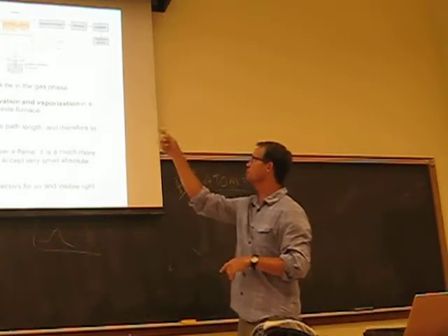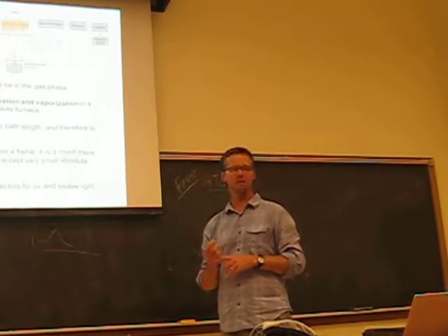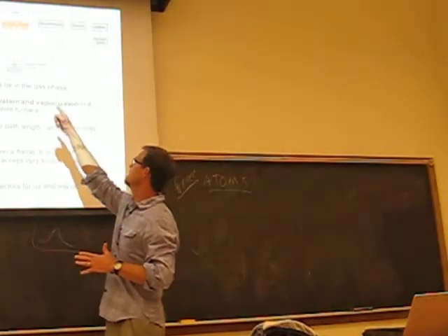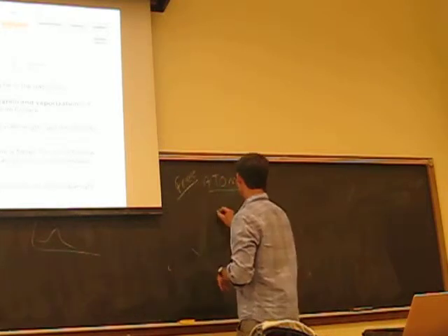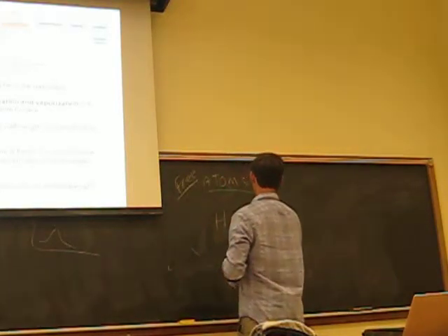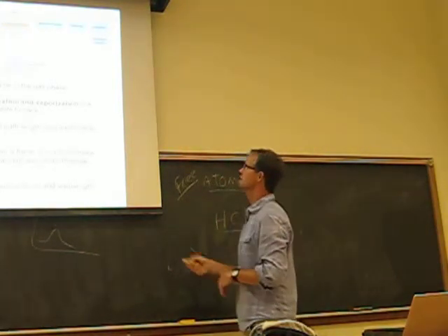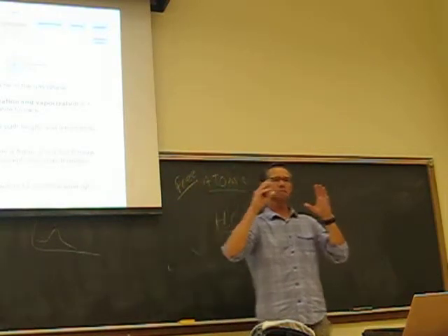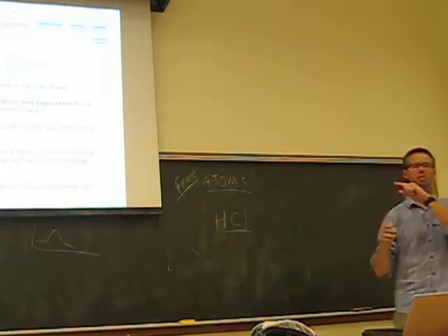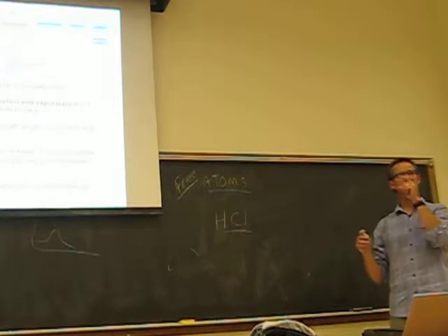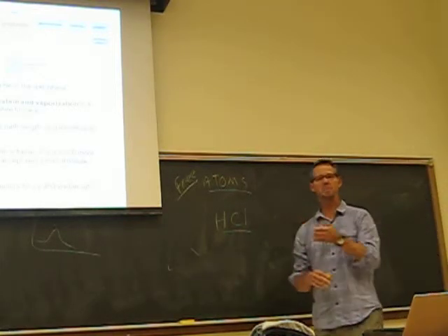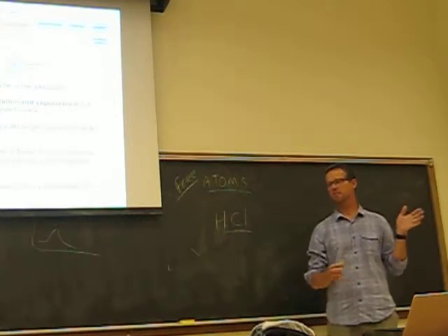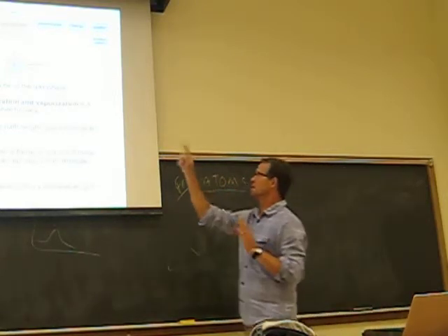And the source of light used in atomic absorption methodologies most commonly is a lamp that's referred to as a hollow cathode lamp, right? And they're abbreviated HCL. And I'll talk about those in detail. So we have a hollow cathode lamp, and in atomic absorption, there's a specific lamp for every different element. So if you're going to measure 20 different elements, you have 20 different lamps at about $500 a pop. Okay? And I'll talk about that.